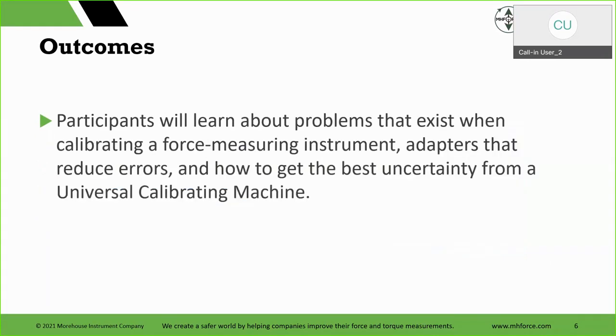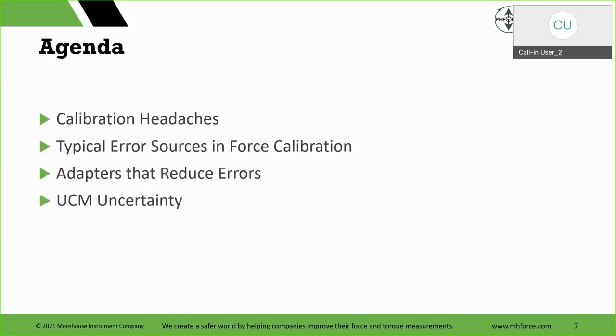Outcomes for today: we'll learn about problems that exist when calibrating force measuring instruments, adapters that reduce errors, and how to get the best uncertainty from a universal cal machine. We'll have a polling question that asks everybody if they're interested in an additional webinar. We do have some guidance documents online, a new website launched, and we have guidance documents on how to do uncertainty budgets for UCMs. I believe that document's 30 some pages. We could do a webinar and walk people through. So we'll ask that question later if that's of interest to people. As of now, we have about an hour to go over things. Typical things we're going to go over here are some calibration headaches, some error sources in force calibration, adapters that reduce these errors, and then some UCM uncertainty, which is only a little piece of it, to show what's going on and what we can do, and that we have this other guidance document.